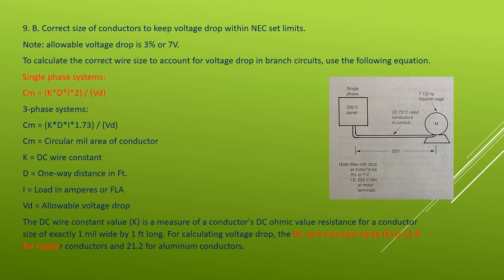For this, we use a formula for circular mils, which is a measure of the cross-section of a cable or wire or conductor. That is equal to the K or DC wire constant times your distance one way in feet times your full load current times 2 for a single phase system. If it was a three phase system, it would be times 1.732. We take all that and divide it by your voltage drop, which in this case is 7 volts.